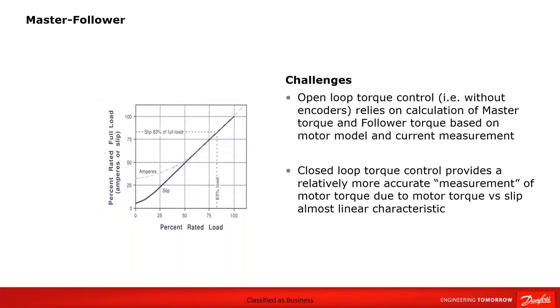So what do we have with open loop with the challenges? Well, open loop torque control. So remember, this is without what we call encoders. It relies on the calculation of the master torque and the follower torque based on what the motor model is and what the current measurement is. So if we want to have better control, closed loop torque control provides a lot more accurate control, a lot more accurate measurement of the motor torque due to the motor torque versus the slip. In other words, you get an almost linear characteristic, and that's because with an encoder, you get your feedback direct from the motor.